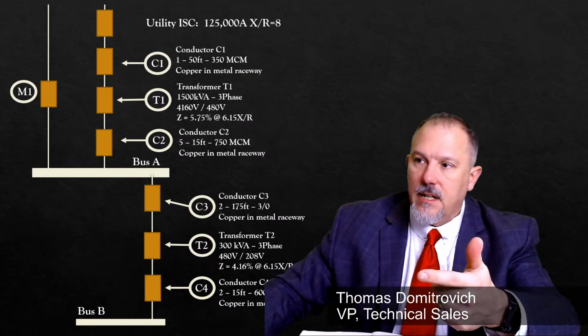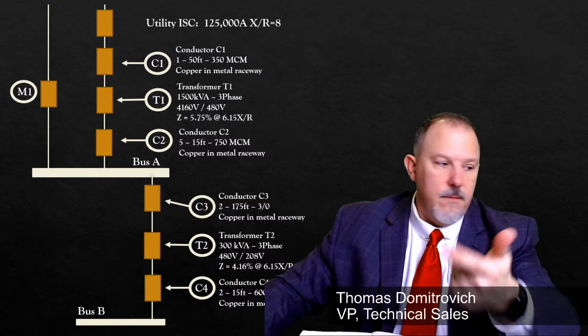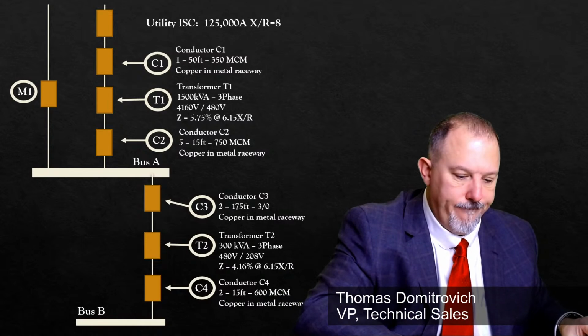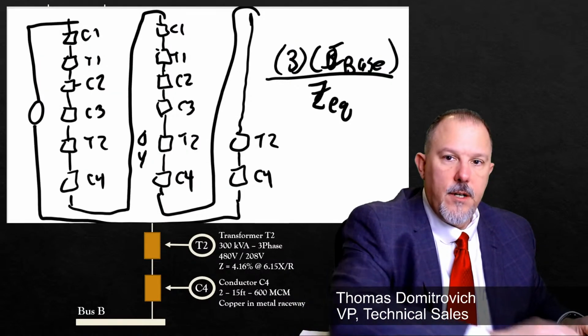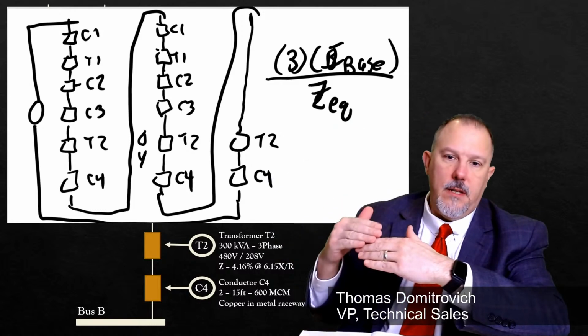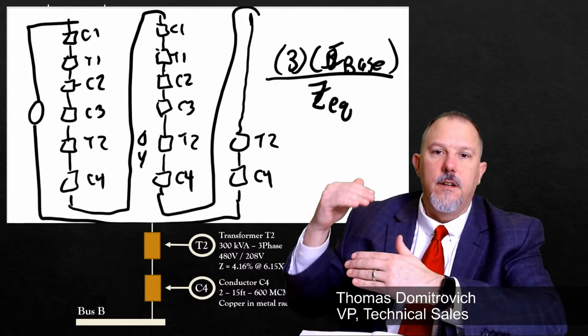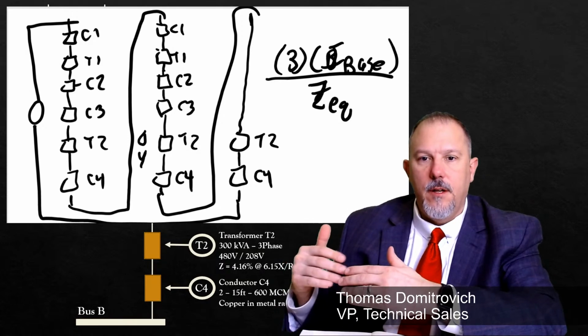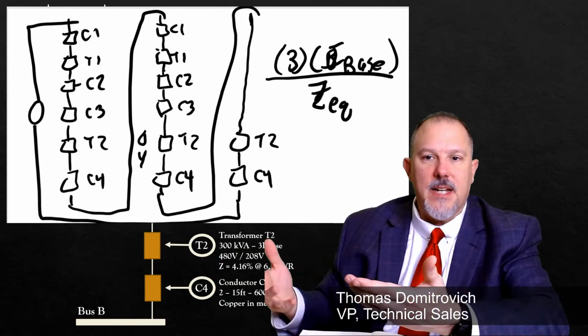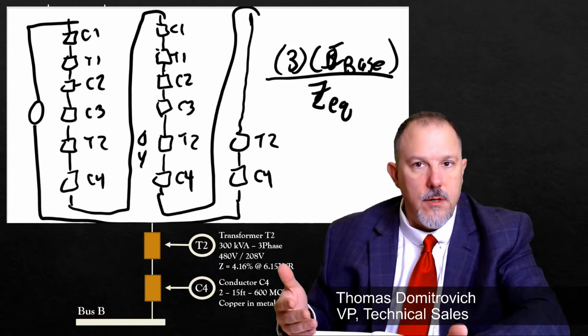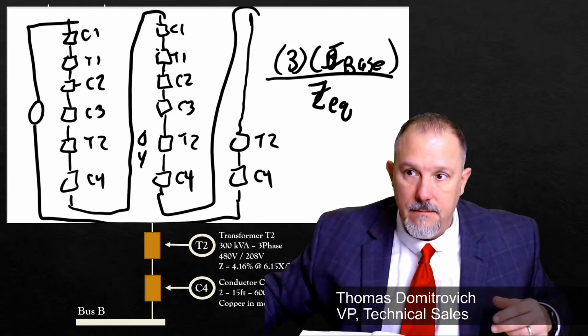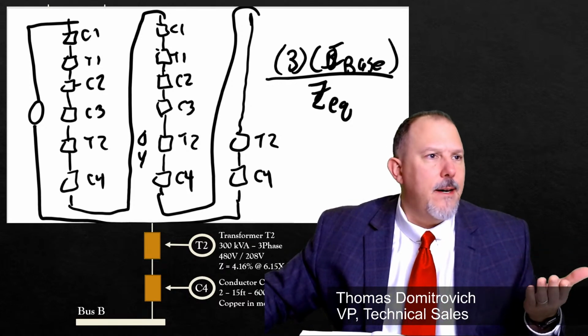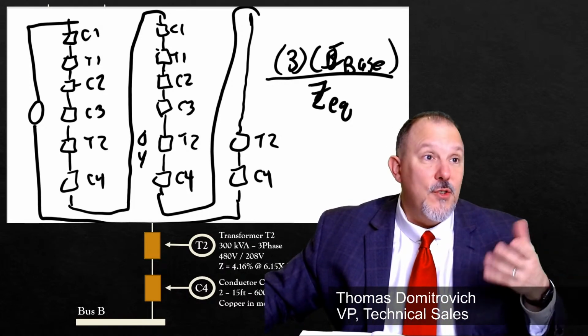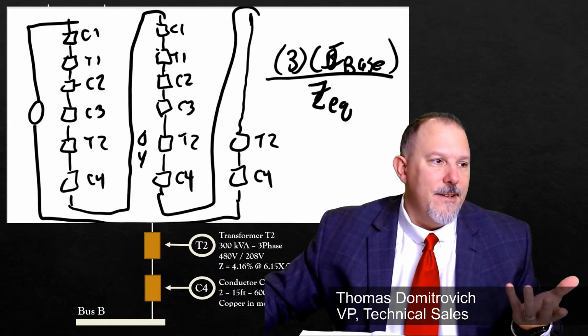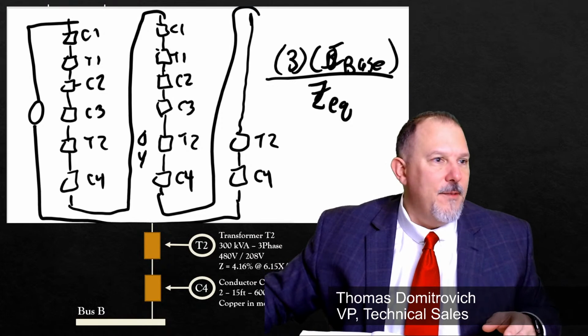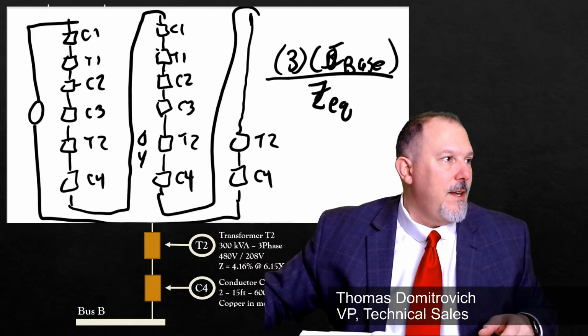But basically, you're going to include all of those impedances and only the impedance on the secondary of that transformer. That's going to be your added impedance. 3 times I base over your equivalent impedance gives you your ground fault current. Makes sense? Is it too much? Are we hitting the right stuff? Do you guys think that makes sense?